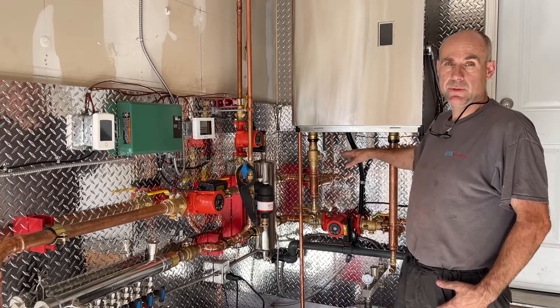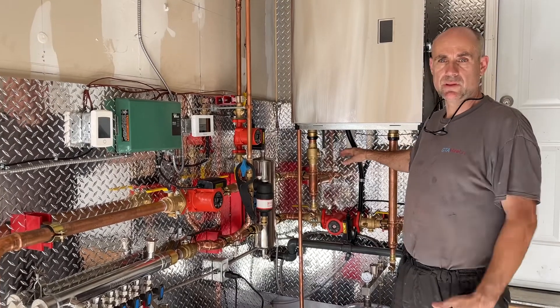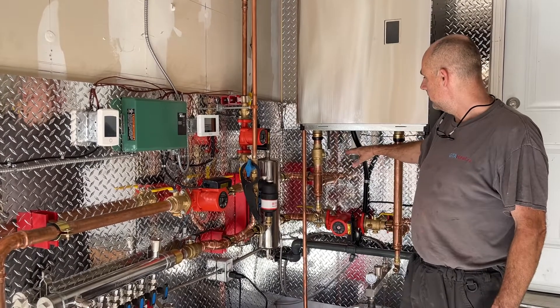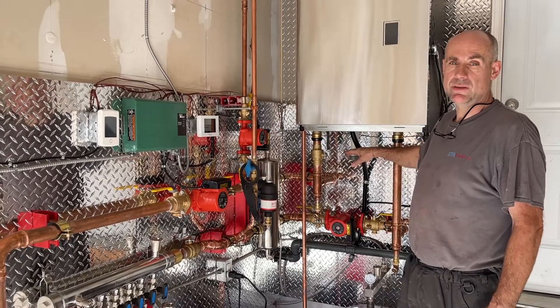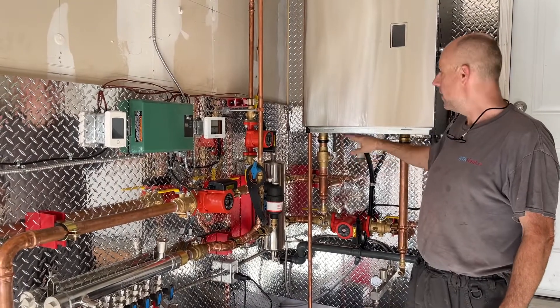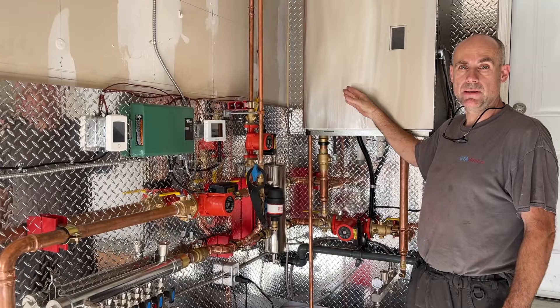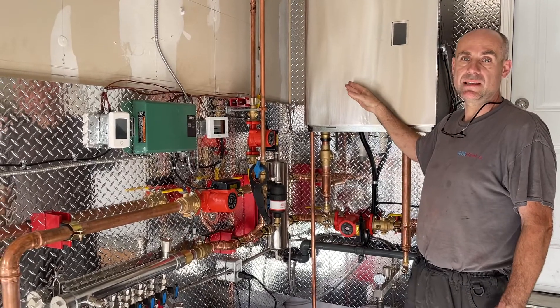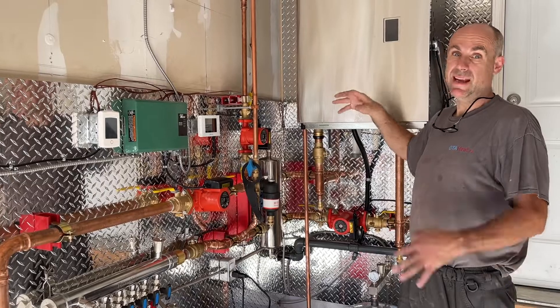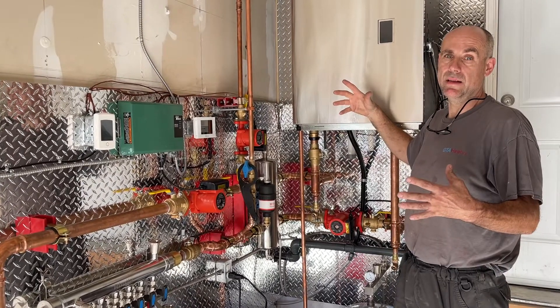The next time the boiler starts up for a snow melt cycle, there is now an ice plug in this trap. Condensation water starts flowing, hits this plug, backs up right into the boiler, and shuts down the boiler because it gets flooded. Then the water freezes inside the heat exchanger and cracks it, more likely than not.